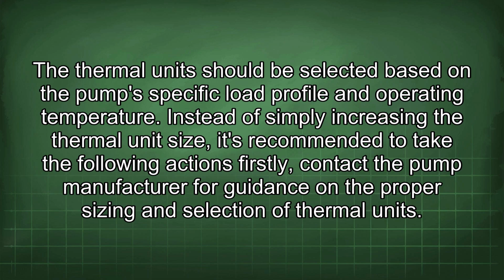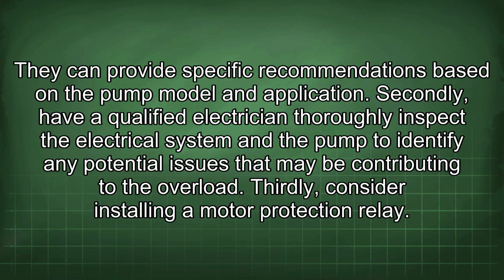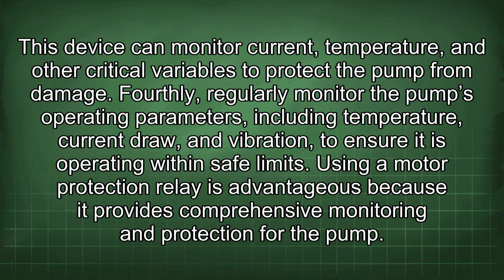Firstly, contact the pump manufacturer for guidance on the proper sizing and selection of thermal units. They can provide specific recommendations based on the pump model and application. Secondly, have a qualified electrician thoroughly inspect the electrical system and the pump to identify any potential issues that may be contributing to the overload. Thirdly, consider installing a motor protection relay. This device can monitor current, temperature, and other critical variables to protect the pump from damage.